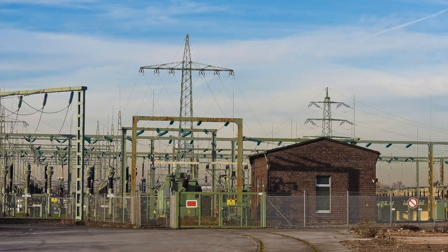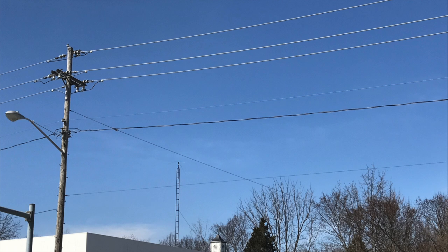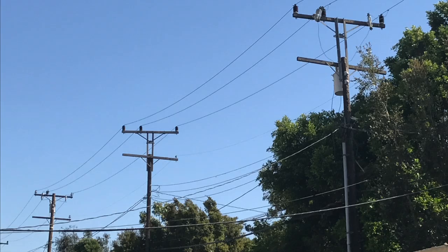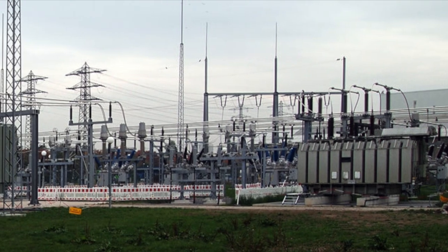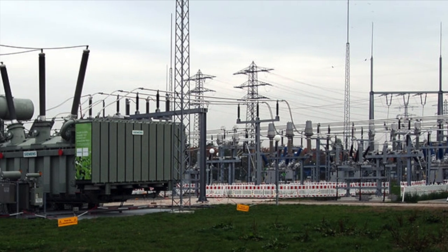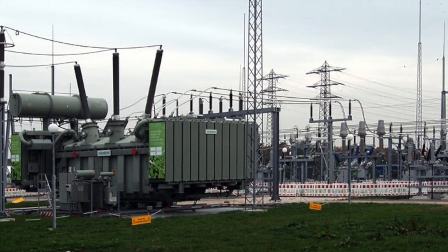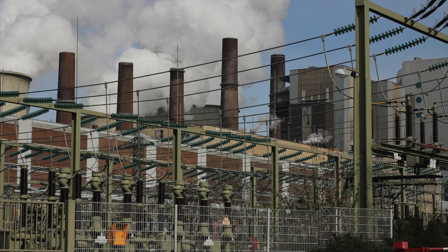Distribution substations use transformers to transfer power from transmission voltages of 115 kilovolts and above down to distribution voltages suitable for local distribution, which range from 2.4 kilovolts up to 33 kilovolts. Distribution substations also serve as voltage regulation points and as points to isolate lines in order to locate faults or de-energize sections. This concludes our coverage of the transmission process.